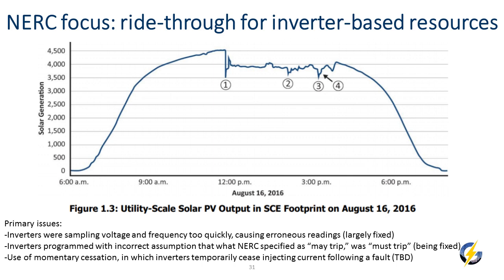This chart shows what happened in the Southern California Edison footprint in Southern California in 2016. A number of PV generators dropped out when there was a fault on the grid. Faults on the grid happen all the time: lightning or something else happens and a transmission line or a large generator goes out, and voltage and frequency swing around. So it's important that the grid be able to withstand that and that the other generators don't go offline when you have an event like that.